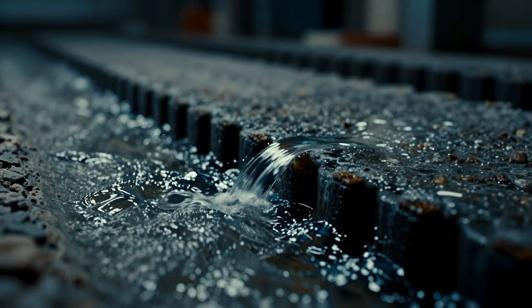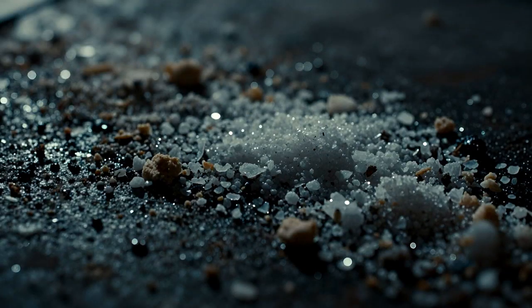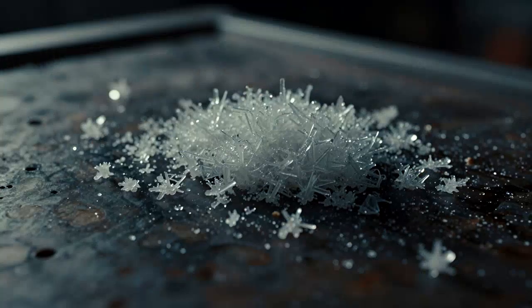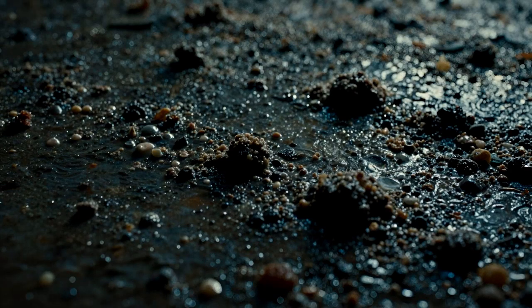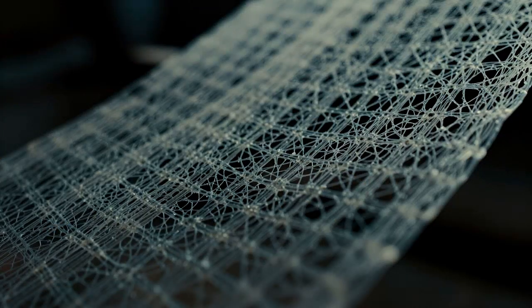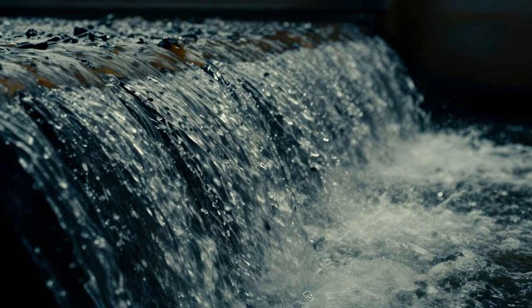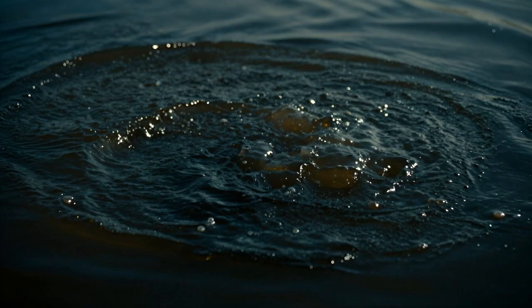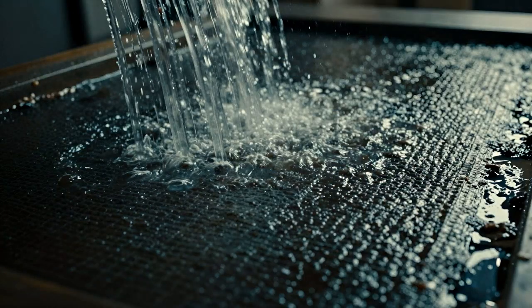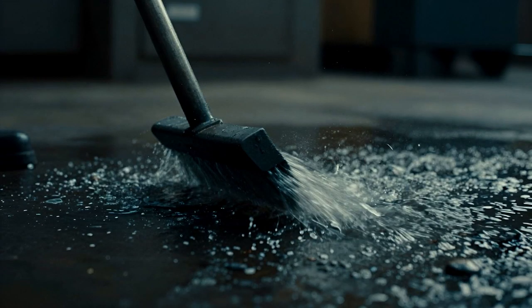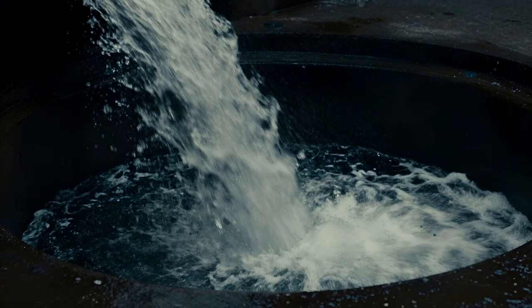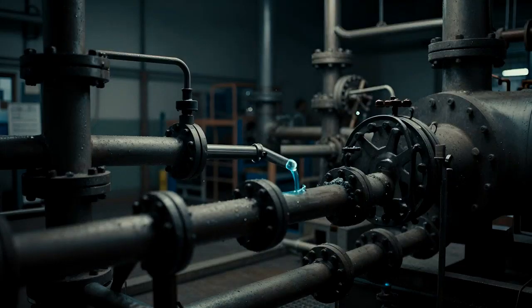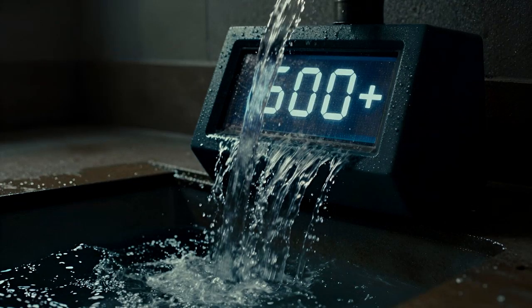However, reverse osmosis systems cannot push 100% of the water through the membrane. If they did, the rejected salts and minerals would instantly crystallize and permanently clog or foul the delicate membrane. Therefore, a continuous high-volume cross-flow of reject water, often called brine or concentrate, must constantly wash over the surface of the membrane to carry the concentrated contaminants away to the drain. This unavoidable operational necessity accounts for the massive 500-plus gallon loss in the ratio.